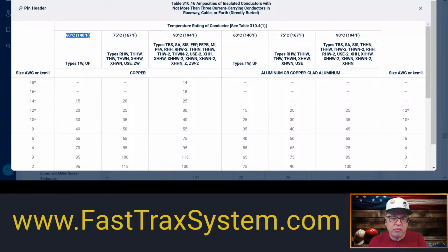Now, that brings us to an interesting topic when it comes to conductors. And I like to point out interesting stuff to everybody, that when you think about a conductor, if it is marked 75 degrees or higher, and even though when you're dealing with the 60 degree column, let's say for THHN, so you may have an ampacity that's less than 100 amps, and you've got conductors that are 14 through 1, and you typically would say, and if nothing's marked, I'm going to use the 60 degree column, and that would be true.